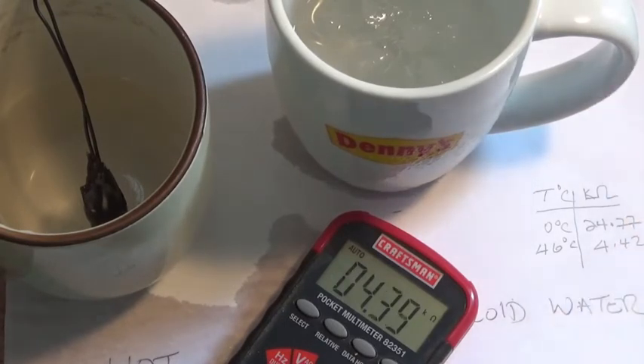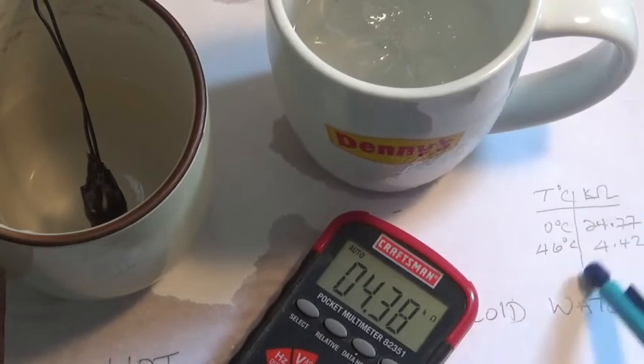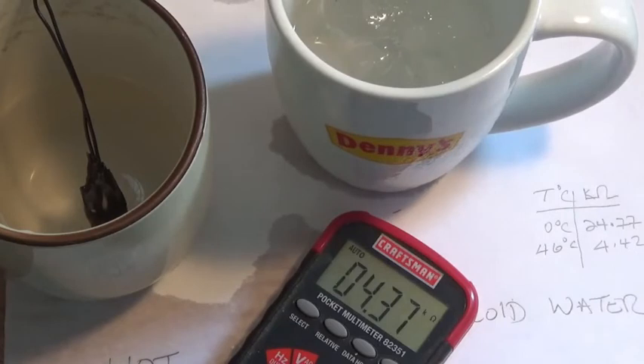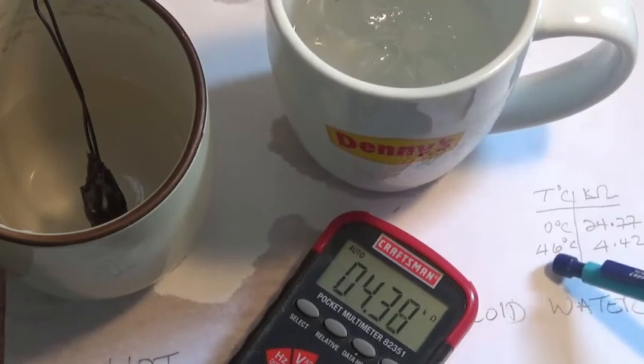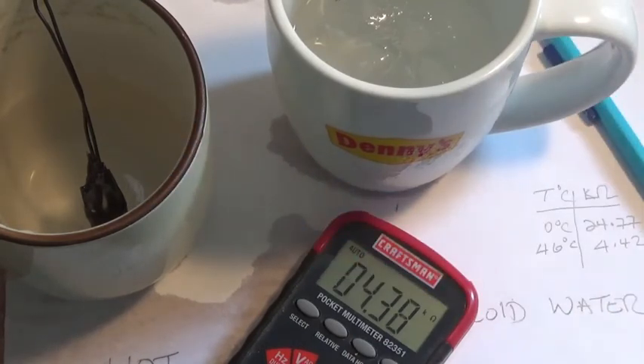Let me see if I can get another temperature hotter than that. So I got 3 points. But at least with these 2 points, there's a big difference in the resistance value. So I definitely can have a very nice calibration curve with those 2 values, at least within this range of temperature. Maybe I want to take a look at what happens when I get this water very hot. Hold it for 1 second here.